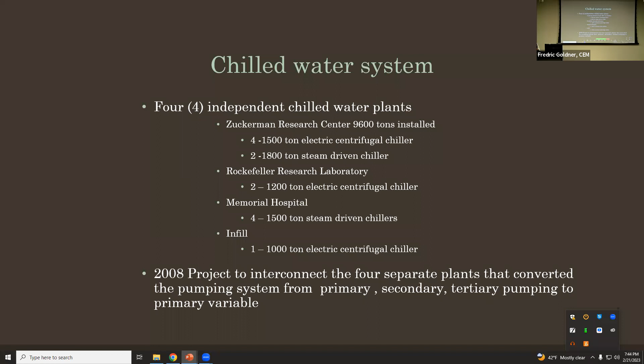In 2008, we went into design and interconnected the 4 separate chilled water plants. The main campus had a primary, secondary, tertiary system. So on each system, we ended up losing about 2 degrees. So by the time we got to the last building, we're producing chilled water at 42 degrees in the plant, but by the time it got out to the building, we're at 46 degrees. And the engineers who had built the building designed the chilled water coils for 44 degrees. So you were already behind the game.